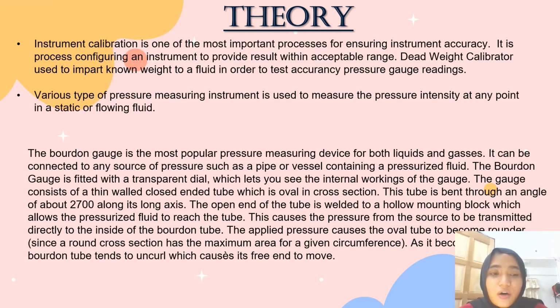So the theory: instrument calibration is one of the most important processes for ensuring instrument accuracy. It is the process of configuring an instrument to provide results within an acceptable range. A dead weight calibrator is used to impart known weight to a fluid in order to test the accuracy of pressure gauge readings. Various types of pressure measurement instruments are used to measure the pressure intensity at any point in a static or flowing fluid. The Bourdon gauge is the most popular pressure measuring device for both liquids and gases. It can be connected to any source of pressure such as a pipe or vessel containing a pressurized fluid.